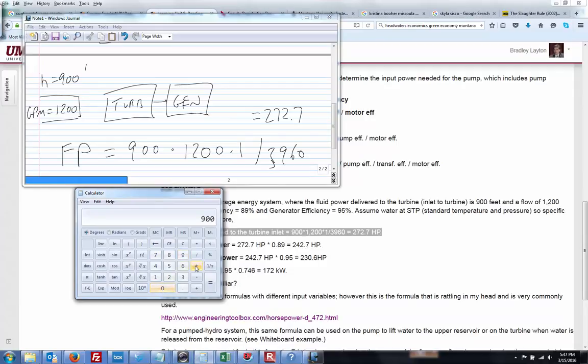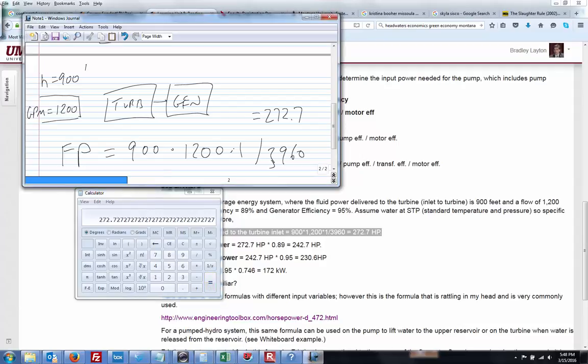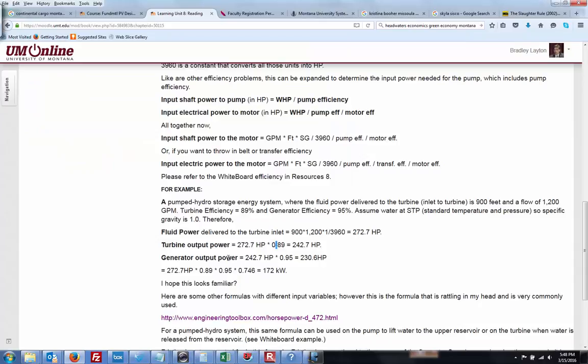900 times 1200, whoops, divided by 3960 equals 272.7. Perfect. Okay, where is that power? That power is right here before it hits the turbine. Then the turbine output, we just multiply that by the 89% efficiency, and we get 242. Then we multiply that by the 95% efficiency, and we get 230.